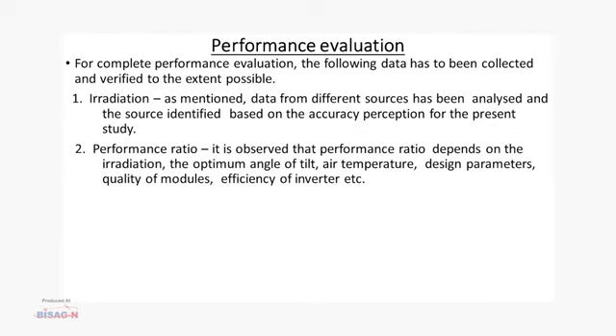Now let us see the performance evaluation of a solar power plant. For complete performance evaluation, the following data has to be collected and verified to the extent possible. Number one is irradiation. As mentioned, data from different sources has been analyzed and the source identified based on the accuracy perception for the present study. Next is performance ratio. It is observed that performance ratio depends on the irradiation, the optimum angle of tilt, air temperature, design parameters, quality of modules and efficiency of inverter.